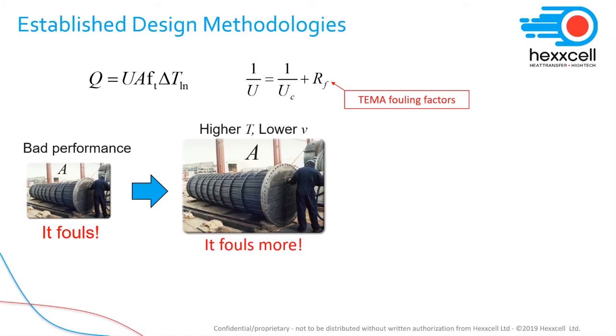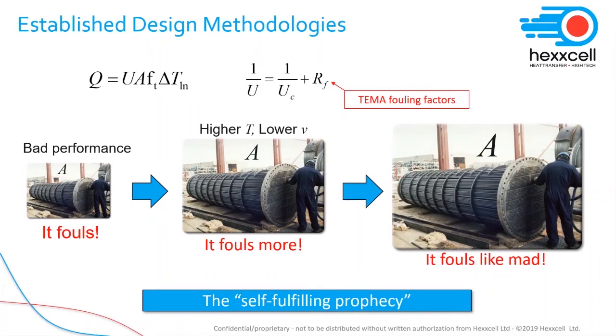However, this increase in the area not only increases capital costs, but it typically results in higher temperatures and lower velocities, which are very often exacerbating conditions for fouling. The overall result is that the heat exchanger fouls more. So we go back to the drawing board and we add a bigger fouling resistance because we thought that the previous value used was not big enough. And guess what? We end up with an even bigger heat exchanger which fouls more. This is what is referred to, and it's not my own definition, as the self-fulfilling prophecy in heat exchanger design.